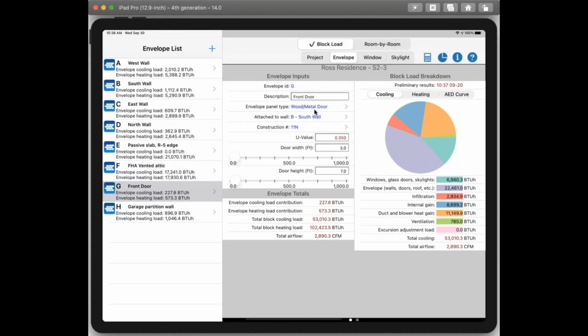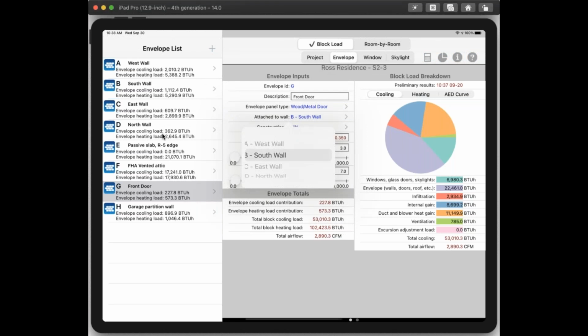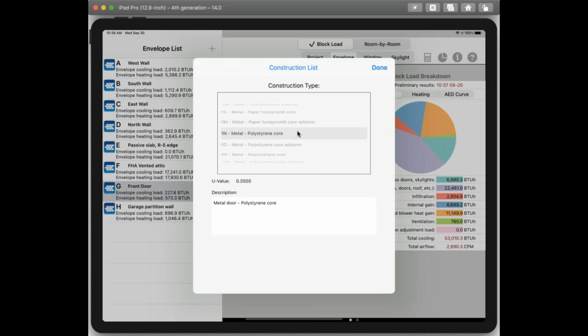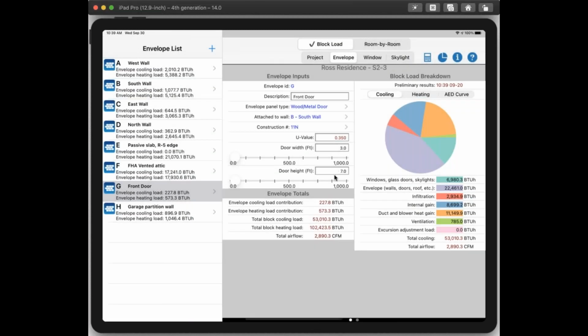Let's talk about door. Here we can select our wood metal door and specify where that door is attached. We defined a bunch of walls already, and we want to specify the wall this door is attached to, because it will subtract out the area of the door from the wall. Here's a couple of different construction types for doors, from the ACCA Manual J8 handbook. Then we fill in the door width and height, the total area, and here's our total load.